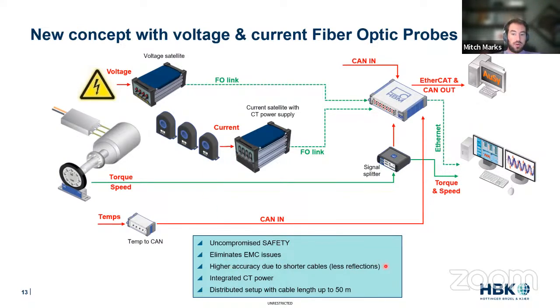Higher accuracy due to shorter cables. I've mentioned this 12 times already. But as we shorten those cables, we lower that capacitance. And with these high slew rate switches, we get into the kind of base physics issues of reflections. Integrated CT power supply is just going to cut down the number of cables you have. Again, lower capacitance, lower cable count, lower ability for noise. And we can distribute these up to 50 meters apart.